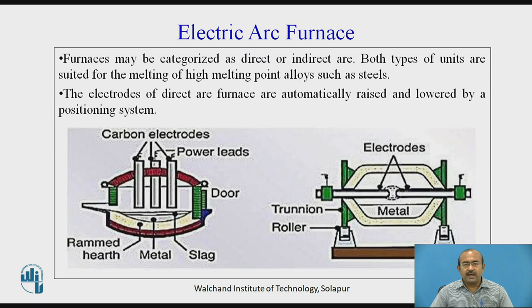Furnaces may be categorized as direct or indirect type, as shown in the figure. Both types are suited for melting high melting point alloys such as steels. In the direct arc type, electrodes are automatically raised and lowered by a positioning system, and an arc is developed between the tip of the electrode and the metal. In the indirect type, an arc is developed between two distinct electrode tips.